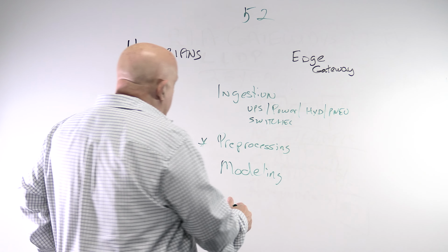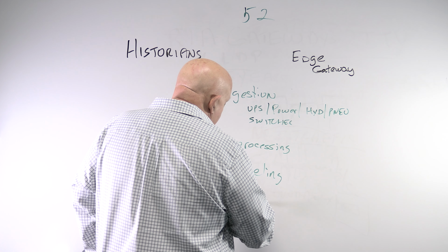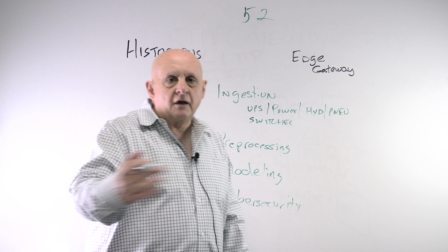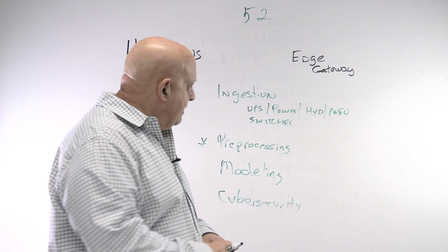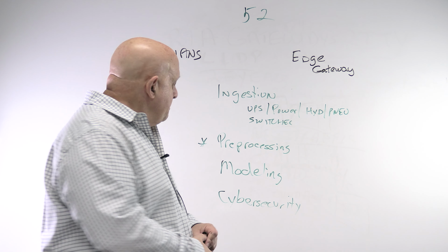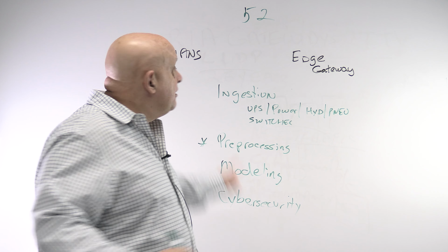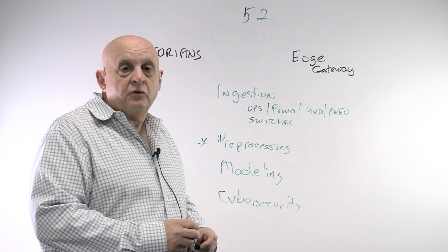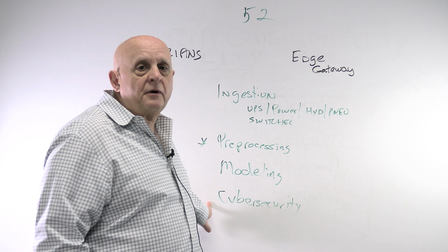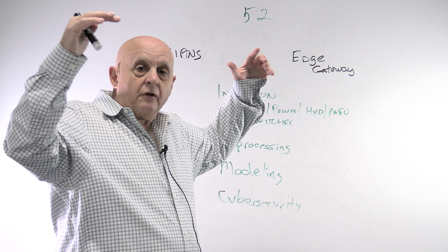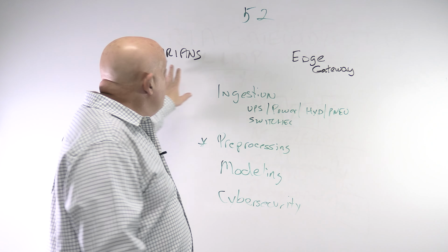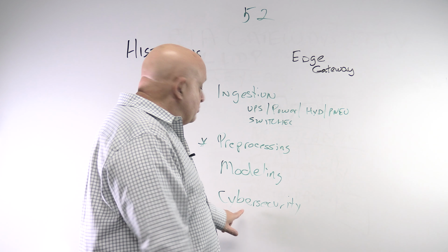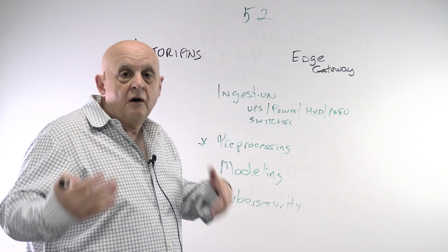And today, the other thing that's really common is cybersecurity, which hasn't been the case for a long time. I've done other discussions on cybersecurity, and that's a great big topic. The thing about cybersecurity is it really matters where you're going to put these. If you're burying them inside your manufacturing system, inside the control system within the firewall, then you don't care a whole lot about cybersecurity because that's going to be taken care of at another level. But if the historian or the edge gateway is going to send data out into the enterprise or the cloud, now cybersecurity is really important, and you have to make sure that you meet the requirements of your plant.